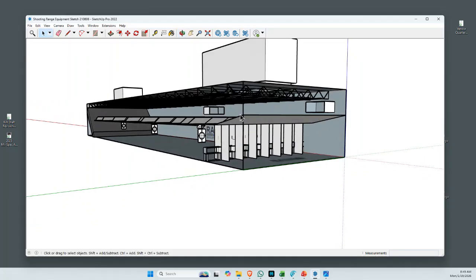All right, final thing I'll mention on wall height. One benefit of hollow core concrete plank is that the walls are lower. With bar joist, you get the advantage of space between the tops of the baffles and the bottom of the joists to run ductwork inside, so it doesn't have to be insulated. Air comes out of the space into the unit, through a filter bank, and is put back into the heated indoor area, protected by the baffles, then runs back up to the unit, is conditioned, and pushed into the diffuser - all that ductwork is inside. Whereas with a hollow core design, you cannot run it inside.